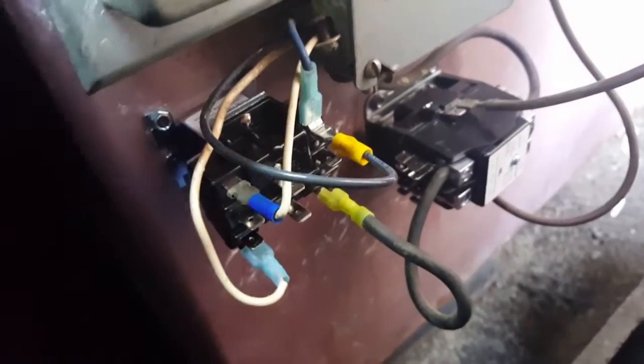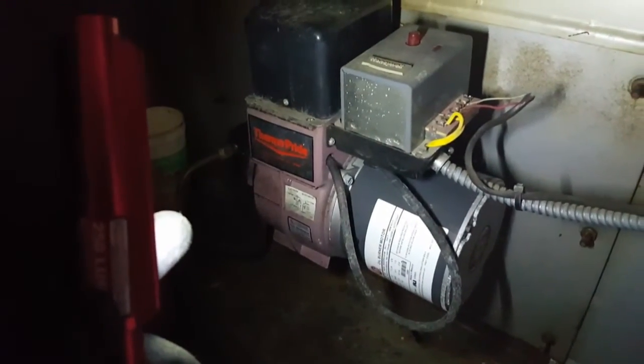Alright guys, all these controls are just to sort of power up the fan in cooling mode. I just copied there. There's the fan and limit control for heating mode. When the heat exchanger heats up, it shuts the fan off. And then it has a limit too, that if it goes over a certain temperature, it'll put it out on limit. It'll cut off the burner here and run the fan.